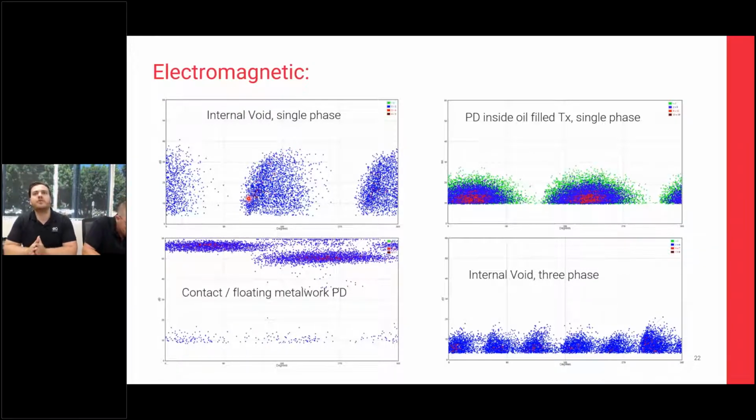We then also talk about a strong leading edge. And that's when you tend to notice the density on this leading edge here on the left is a lot denser. And in some of our examples, you'll see the textbook example of that, where it's got a really strong leading edge going up into a wave. And that is your cliche type internal void discharge.